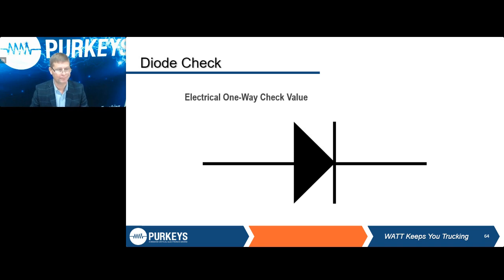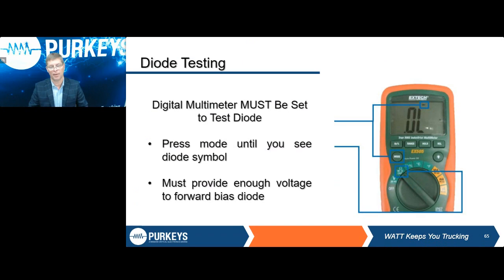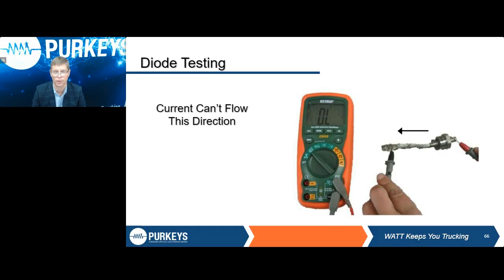Whenever you're using your meter, you've got to make sure you look at your knob setting and also at your screen. Some meters have a dedicated diode check. Some of them, it's a shared function. So if you look on the screen right now, it's an ohm meter, it's a diode check, continuity check, and also a capacitance check. So you may have to use that mode button and toggle through until you see the little diode symbol come up on the screen. Can you use an ohm meter to check a diode? Technically, yes, you can. Is it a fair, accurate test? No. You should always use diode check to check a diode. We've got a couple different examples here of just what they would show you or not show you.